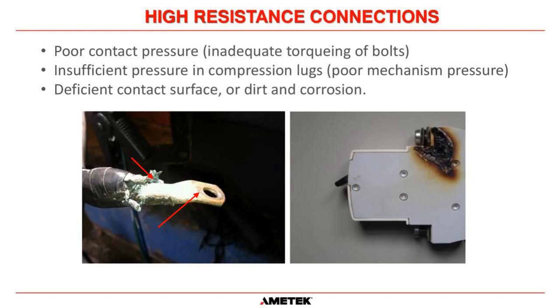And what's the problem with high resistance connections? Well, high resistance connections cause voltage drop, which then causes heat with power dissipation. And you can see on the right-hand picture there on that small circuit breaker that there has obviously been a loose connection, and it's been there for a while, and with current flowing through that connection, the power dissipated has been very high, and it has caused a severe amount of damage to that circuit breaker. Now I would guess that this is a very small circuit breaker, maybe 10 maybe 15 amps, and our UPSs go from 10, 15 kVA up to 200 kVA. So we have a much larger amount of current flowing through our power connections, so we can cause a lot more damage by high resistance connections. Okay. So that is one mode of failure, high resistance connections.